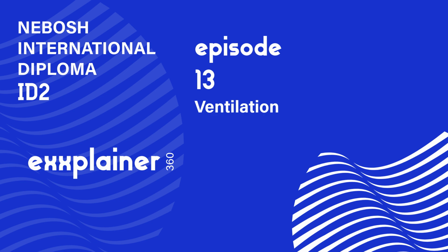But you said it sounds simpler, implies limitations. Huge limitations. Because it's so basic, DV really only works for a couple of things. Either keeping flammable vapors below their lower explosive limit, the LEL, so they don't go boom. Precisely, or keeping toxic stuff below its occupational exposure limit, the OEL. But there are big ifs. Okay, what are the ifs? Why can't I just use this for everything, like welding fumes?